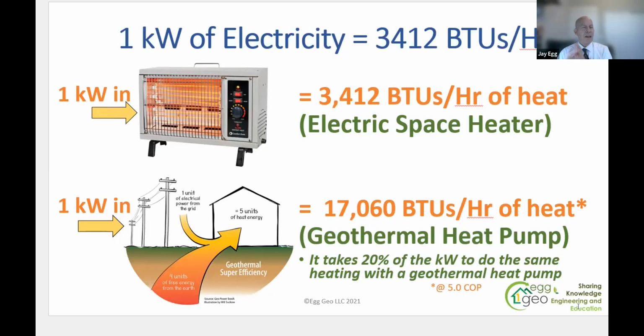The other way to look at this is if you use 1 kilowatt of electricity in an electric heater like you see here, 1 kilowatt will deliver 3,412 BTUs per hour of heat. That's just very simple equations, because we just talked about that in the last slide. However, if you use a heat pump, that 1 kilowatt of electricity will deliver 17,060 BTUs of heat, especially with a geothermal heat pump rated at a coefficient of performance of 5. And you can see in this image very simply how that's done. A geothermal heat pump using 1 kilowatt of electricity will be able to pump another 4 kilowatts of heat out of the ground because it's a heat pump, delivering a grand total of 5 kilowatts of energy.